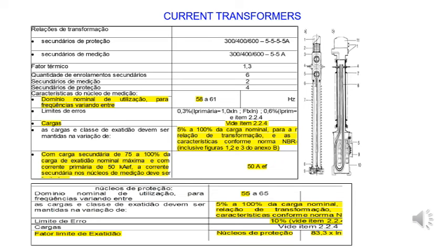When you have one protection core and one very high current, a short-circuit current, passing through the current transformer, the image in the secondary side shall be a perfect image of the current which is passing. And there is one test to check this. In the same way, there is a test to check the passage of the rated currents of the current transformer.